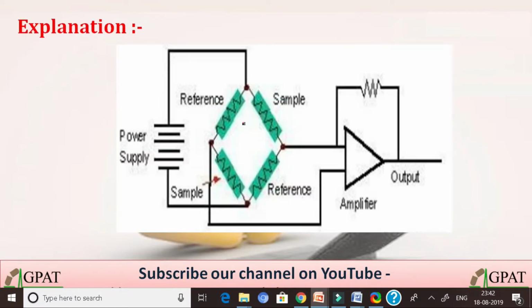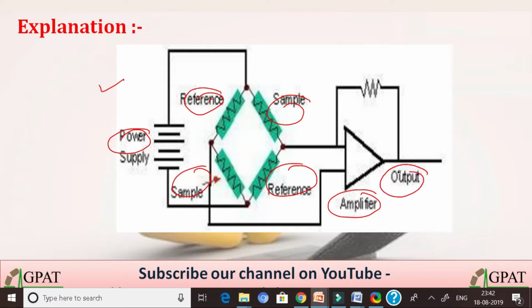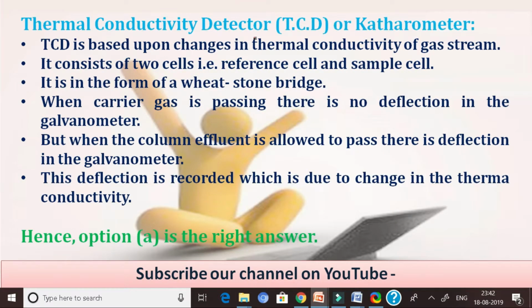Here we have just a simple explanation of the catharometer. You can just write down or understand that here we have a power supply, this one is reference, and this one is our sample. So through an amplifier we get the readings and it's the output. Here is some information about the TCD, thermal conductivity detector or catharometer, that it is based on changes in thermal conductivity of a gas stream. It consists of two cells, that is the reference cell as well as the sample cell, as we have already observed in the diagram.